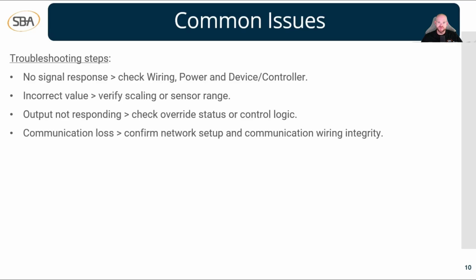The next one here, we're talking about software. Troubleshooting steps for an incorrect value within our software. This one could be a configuration issue. So I would probably start in the software and make sure that our scaling and our sensor ranges are set as they should be. Again, you're going to have to set these ranges when you go into the configuration, and if you get them wrong, they won't read right. So you've got to go back, verify those, and if they're wrong, fix them.